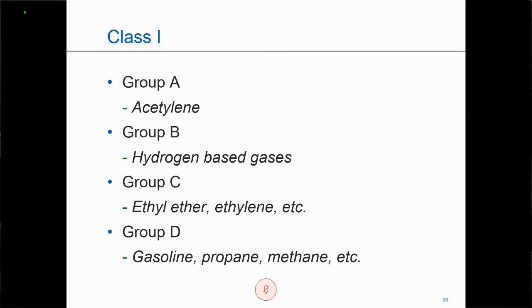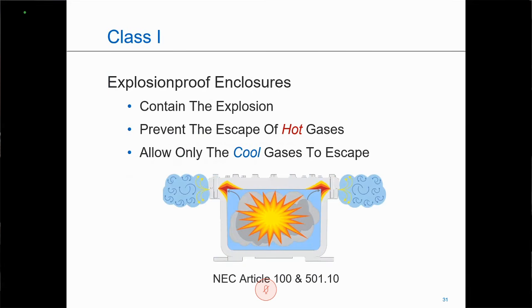So when a manufacturer is producing equipment to be used in hazardous location areas, it's extremely important for us to understand what these gas groups are, to make sure that that piece of equipment has been approved for that area and will operate safely in that area. And the reason for that is that explosion-proof enclosures, when we're using the NEMA 7 explosion-proof protection technique, contain the explosion, cool the hot gases, and then harmlessly release those cool gases back out to the atmosphere. So we need to make sure that the gas group that's exploding inside or could explode inside is approved for that unit, so the unit doesn't rupture or fracture when it's containing the explosion.